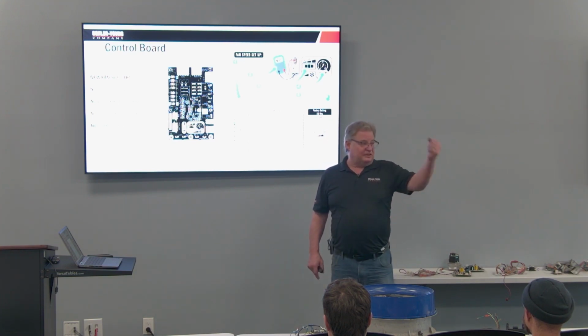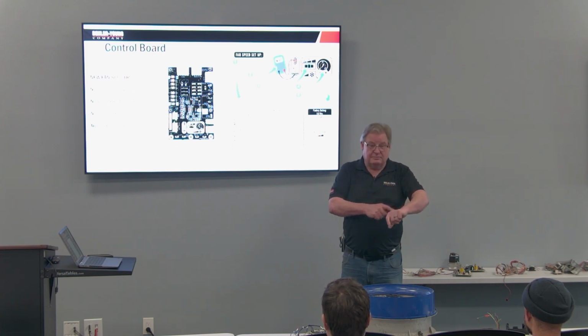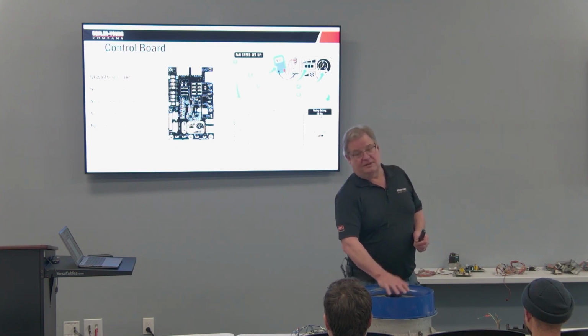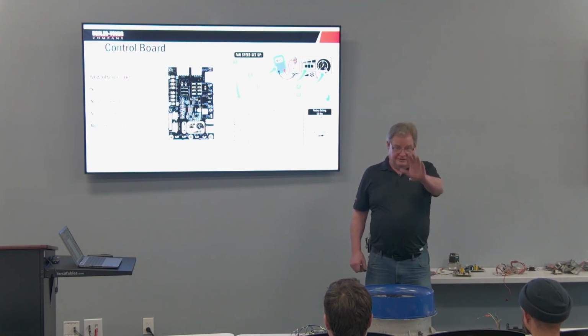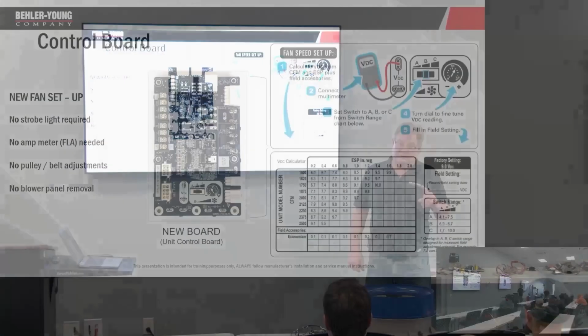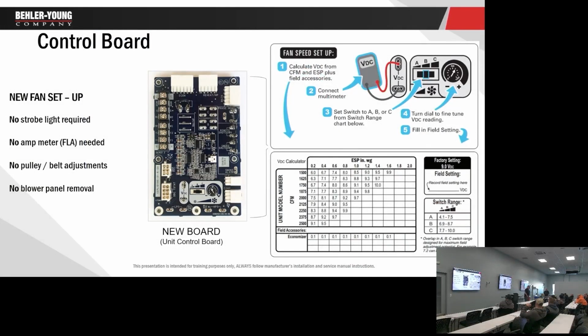So before you fault one of these motors, the first thing you want to do is throw the disconnect for 3 minutes. We are service people. We have no patience. I have really little patience. 3 minutes seems like an eternity. Look at your watch, because the capacitors inside this motor have to discharge before it'll reset. 3 minutes, turn the disconnect back on. Oh, the motor's running. There's nothing wrong with the motor. There was a power issue that caused it, or the static pressure wasn't set up correctly.